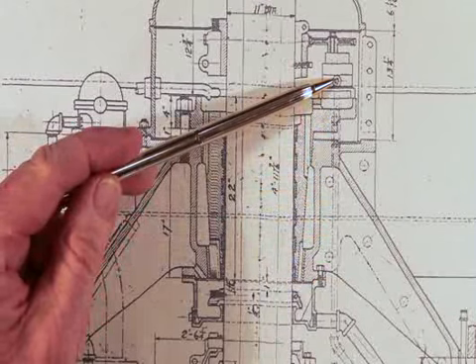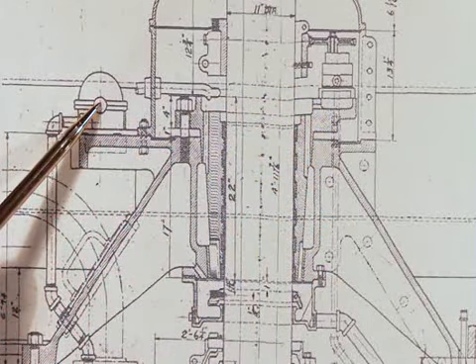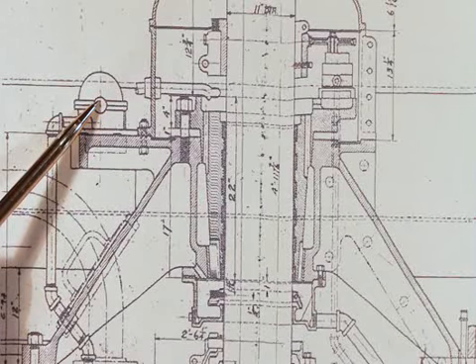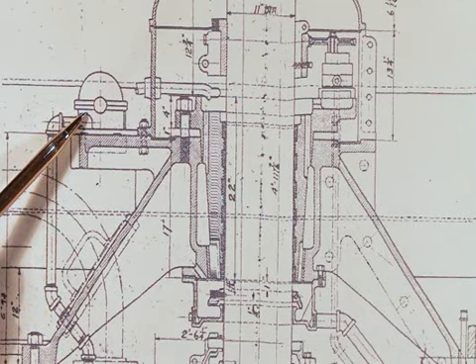In addition to this shaft-driven gear pump, there are 2 additional external electrically driven oil pumps that will continue to supply oil to the upper guide bearing and main thrust bearing located at the generator level, but not to the converted lower guide bearing.